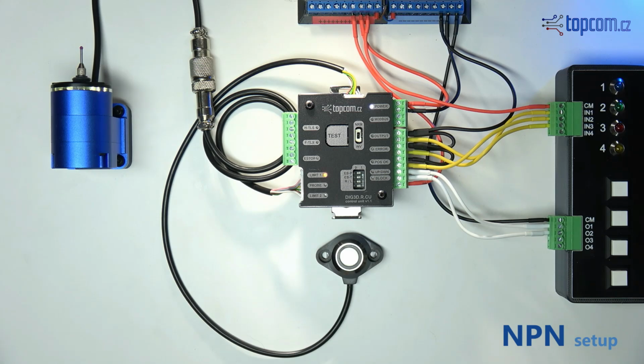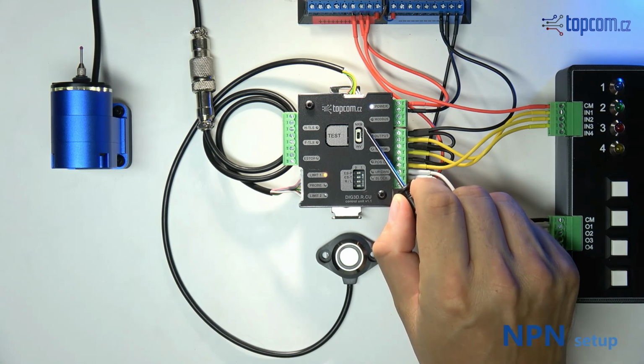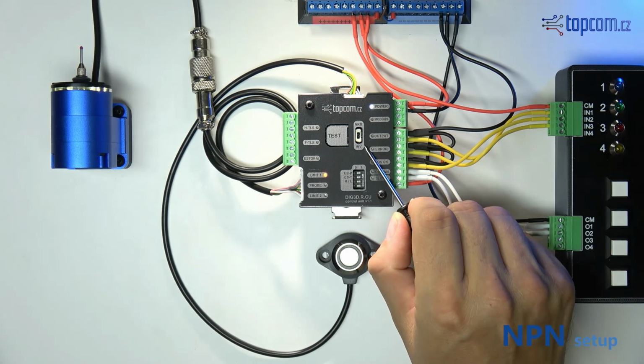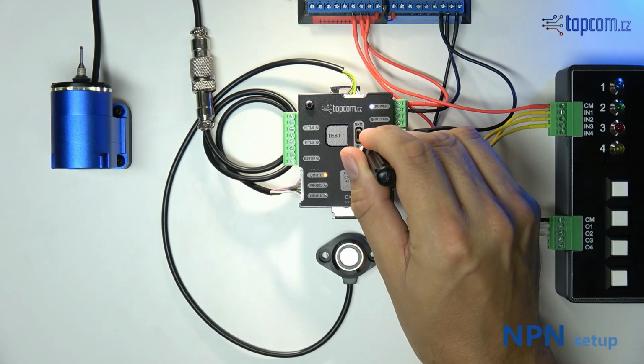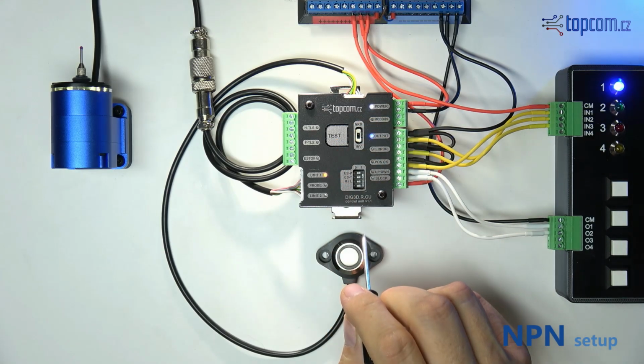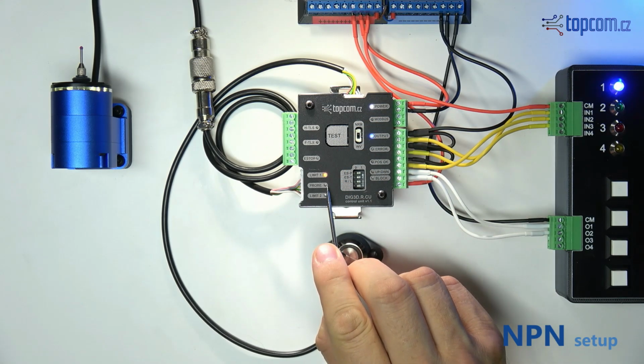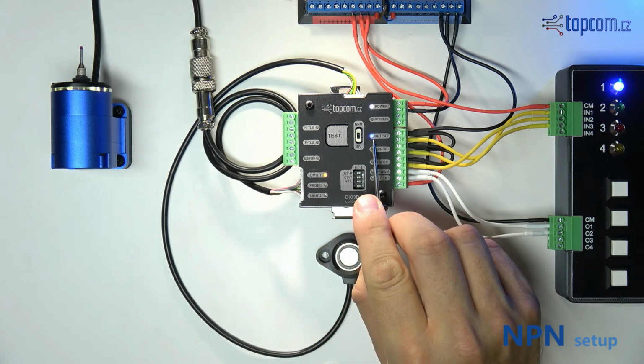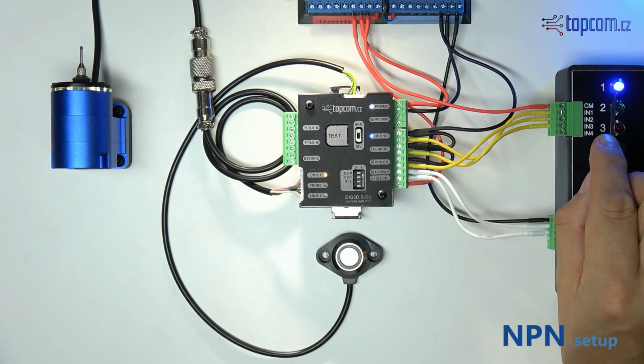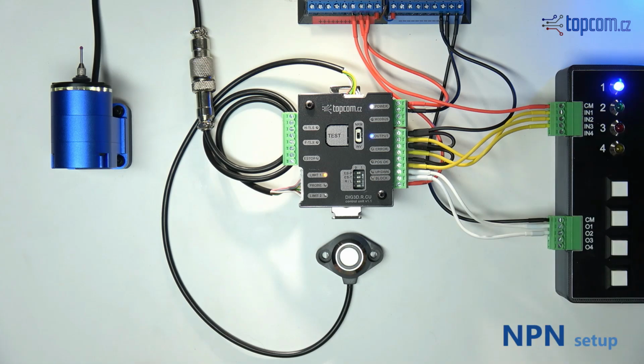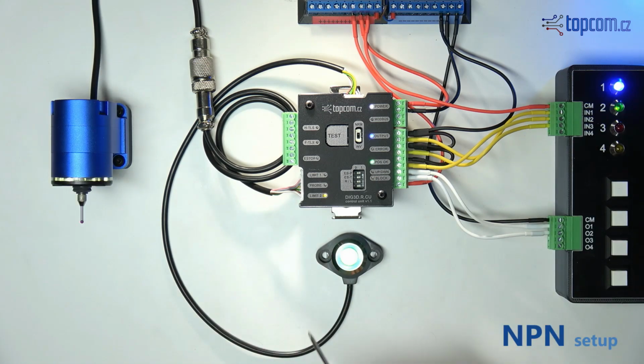The control unit includes a switch for setting the output polarity of the probe signal. It can be set to either normal or inverted. Normal corresponds to a normally open switch, meaning the output is active only when the probe is triggered. In inverted mode, the output is active while the probe is idle and deactivates when the probe is triggered. This setting applies to all connected probes and sensors.